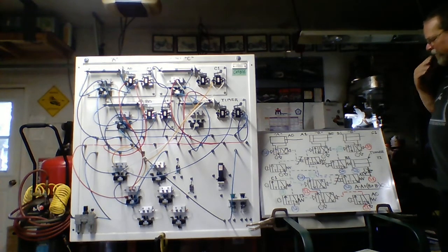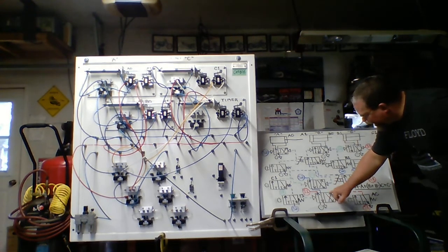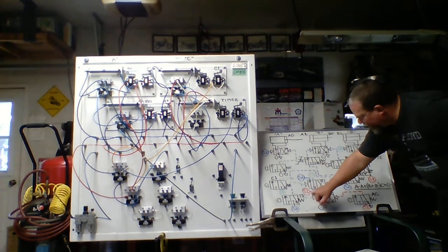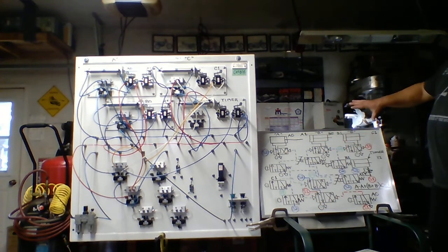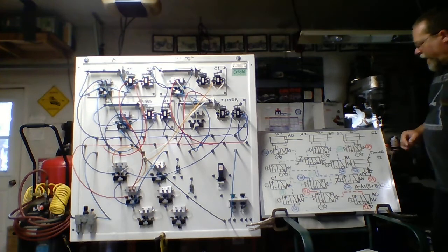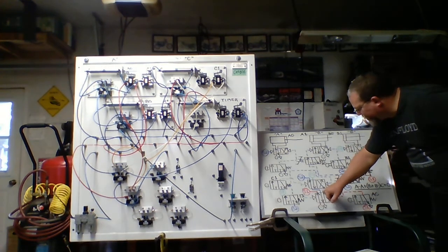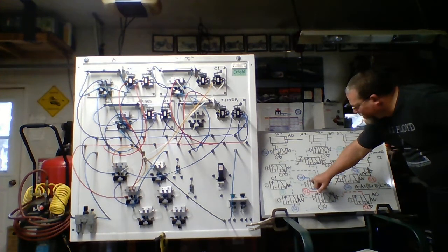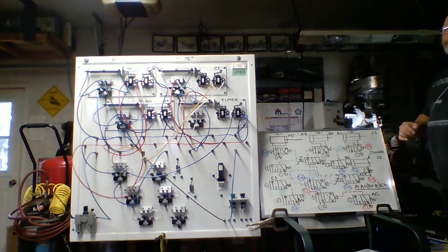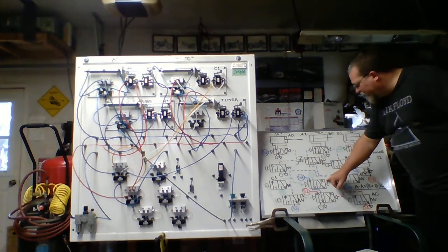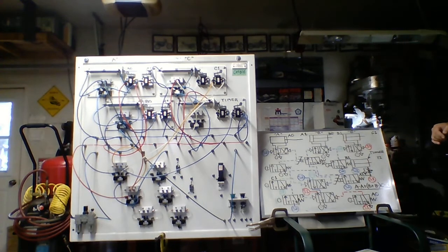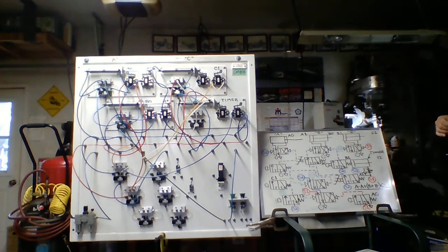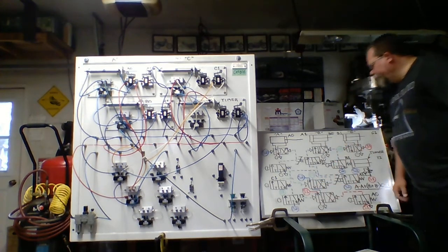So looking at the design here, the 2 cascade valves, here's the first one, main source, and you can see the flow path is open, so source 1 right now is available as this sits idle or static, ready to go. And when we shift the first cascade valve from right to left, you can see the supply line here, source 2. The second cascade valve has an open flow path, and of course we have source 2 available. Once we shift the second cascade valve, then of course we'll have source 3. And in the end, we have 2 pilot signals here that will bring both cascade valves back into home position, which brings it right back to source 1.